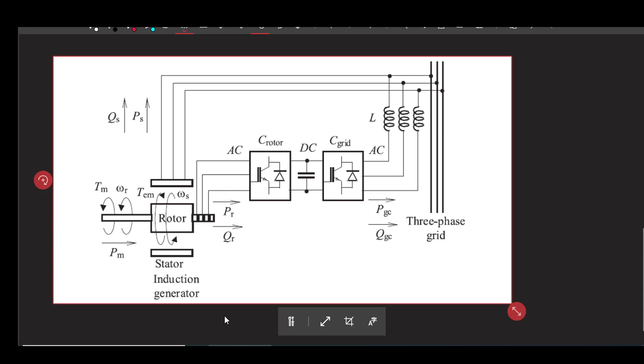The obvious question is, why do we need this at all? The answer is that this sometimes addresses why there is poor power factor, or why the induction generator needs such a huge amount of reactive power during its start. The reason is the air gap and the need to magnetize the core, but if you somehow allow flow of current through the winding during start through this arrangement, then that job is done, giving an additional benefit.